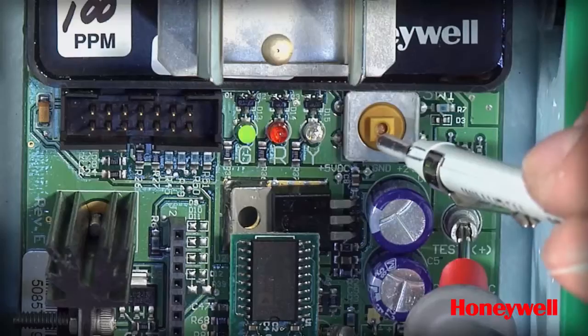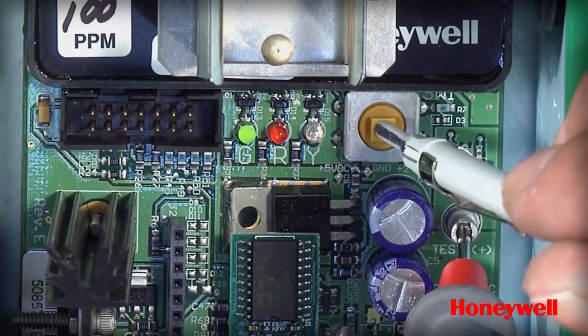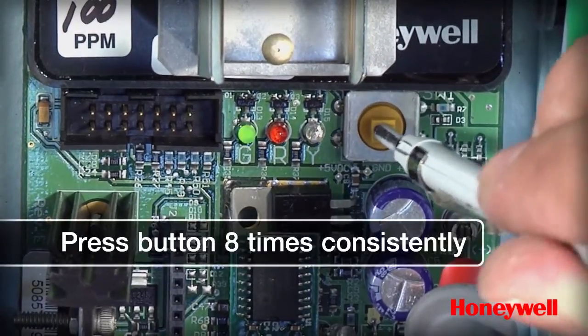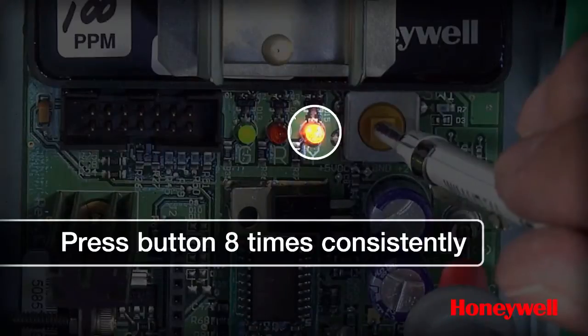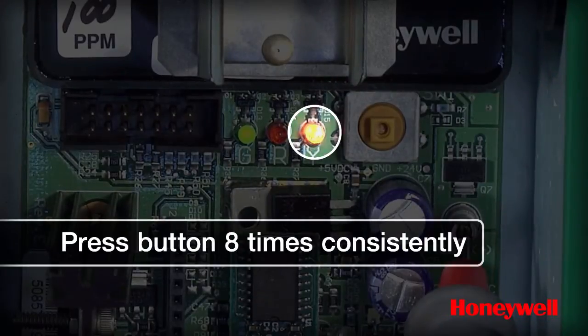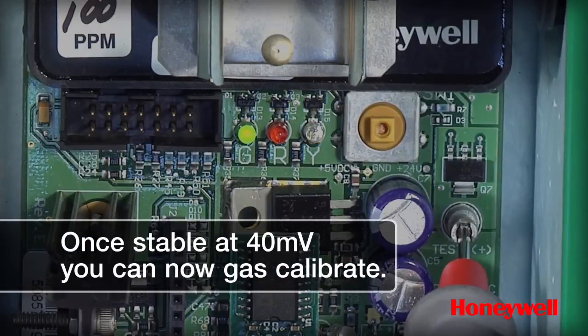Now you must internally zero the unit. Press the button 8 times swiftly and consistently until the yellow LED flashes slowly. This EC-FX is now zeroed and outputting the desired 40 millivolts. After performing the internal zero process, it can take up to 5 minutes to stabilize.